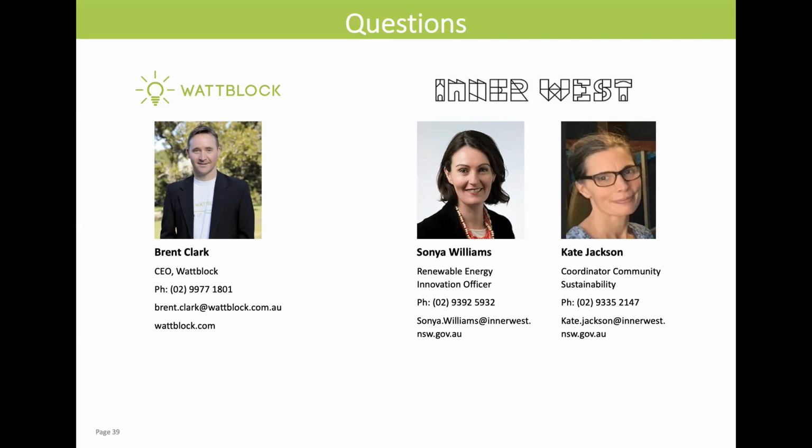Are there any rebates to encourage strata blocks to update to smart meters in order to get solar fitted? From Claire. Yeah, not in New South Wales. As we know, in Victoria, they mandated smart meters across the entire state, and it was done as a project. In New South Wales, it's an organic process, but the responsibility of the owners corporation is to update the meter board to get enough space. And then a lot of these smart meters, if you call up AGL and you've got a compliant meter board, they'll come and put a smart meter in even for a tenant or a renter at no cost.